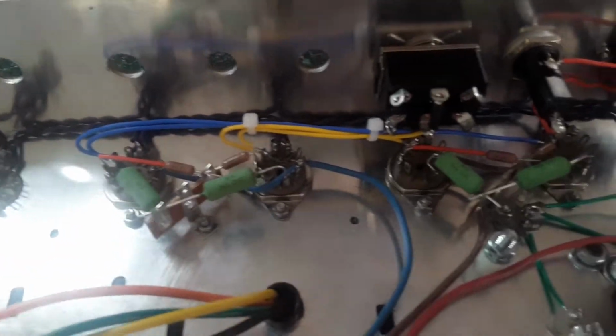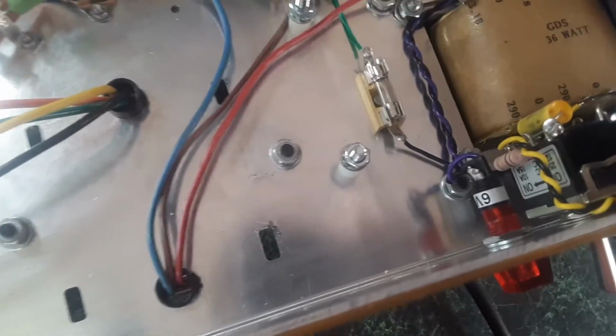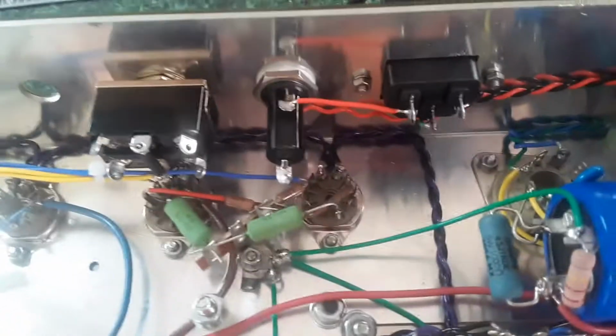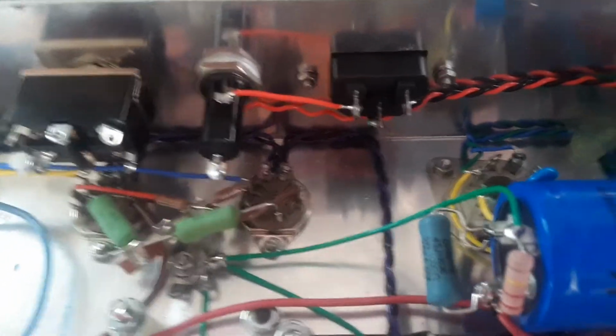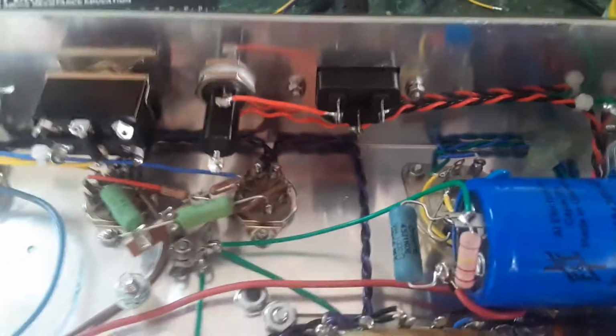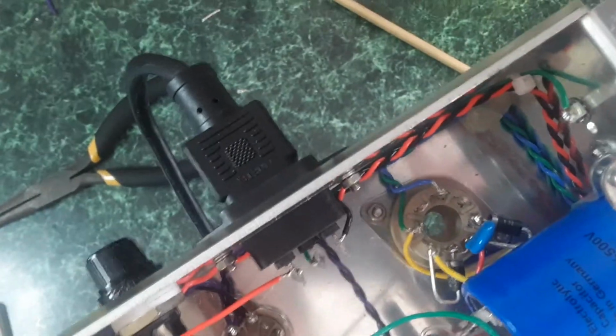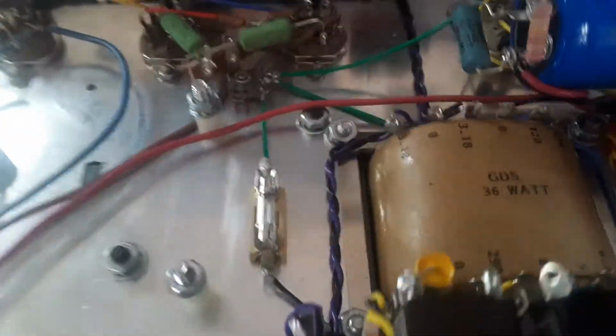I actually already had this powered up because I took test readings of all the voltages across all the tube pins, and they all look perfect. I also took voltage readings at the indicator light, and that's correct. I also took readings on the inside of the IEC connector. All of the high voltage and low voltage readings are accurate.